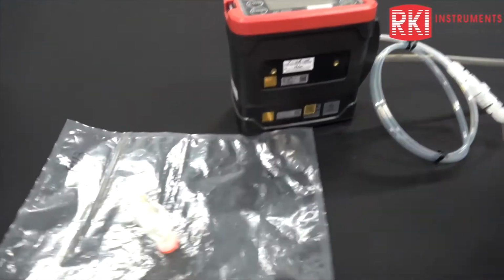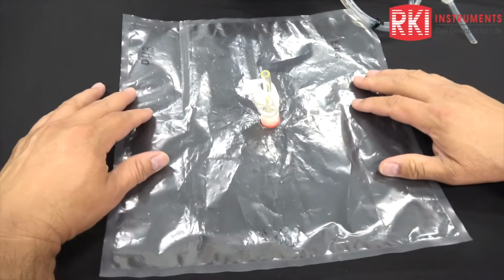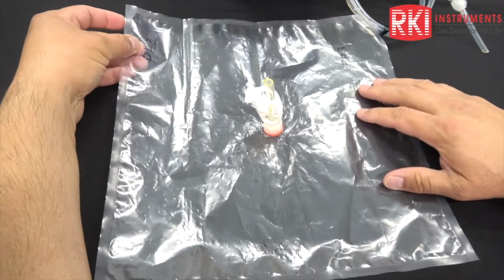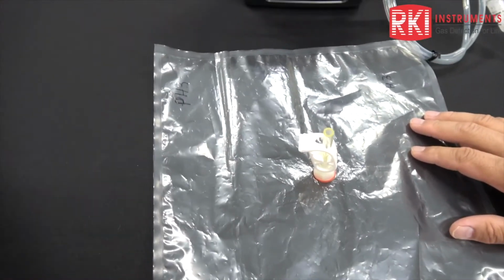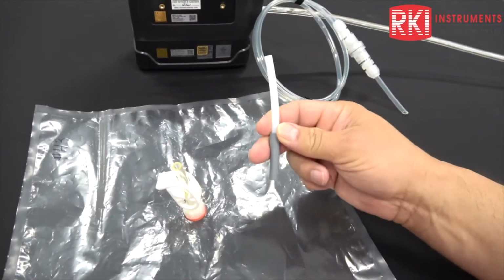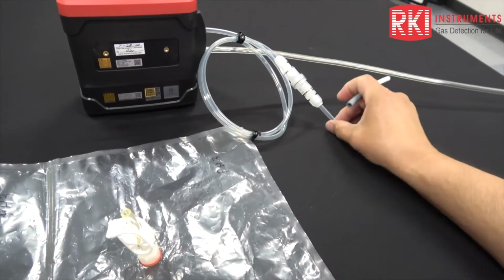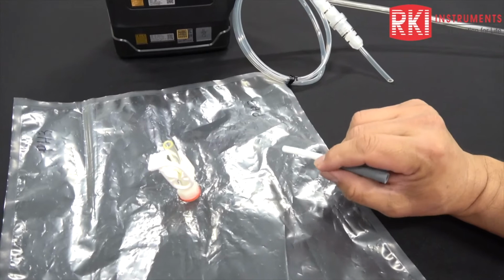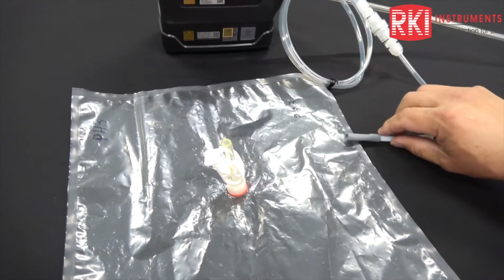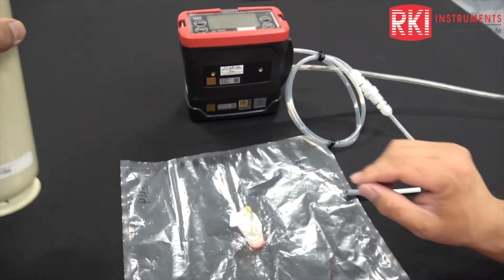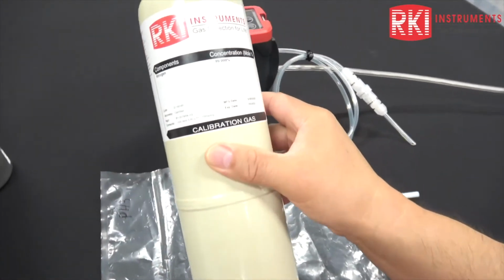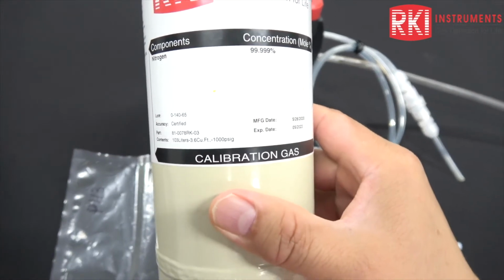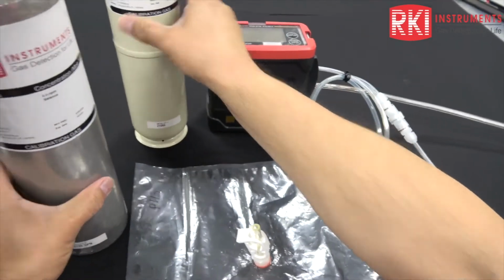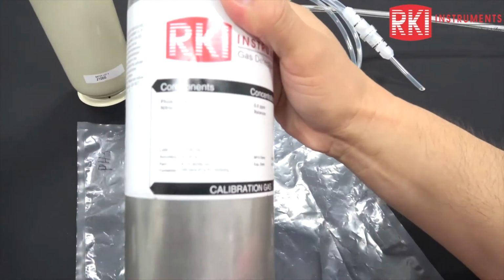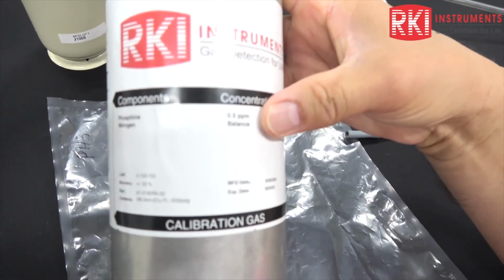Over here is a 12-inch by 12-inch Tedlar calibration bag. And we have this particular one marked with pH3 for phosphine. And I've also got a couple little pieces of adapter tubing that we'll be using in conjunction with the probe tip and interfacing with the calibration bag there. And then we've also got a couple of calibration cylinders, of course. This is nitrogen, almost 100% nitrogen, 99.999%. And we'll be using that to dilute our phosphine sample down, which is phosphine and nitrogen at half a ppm, which would be too high for a calibration level. So that's why we want to dilute it down.